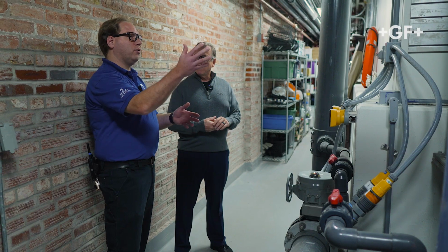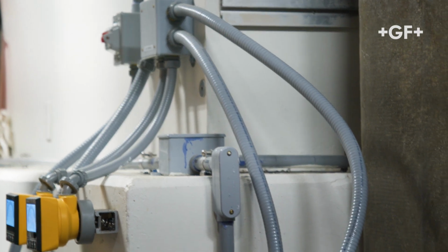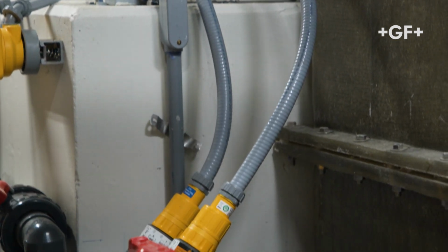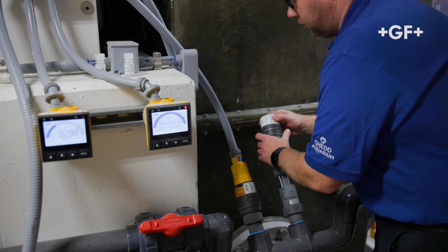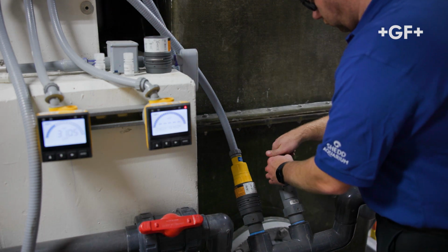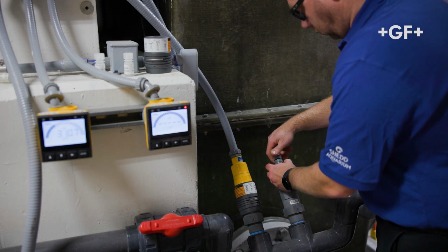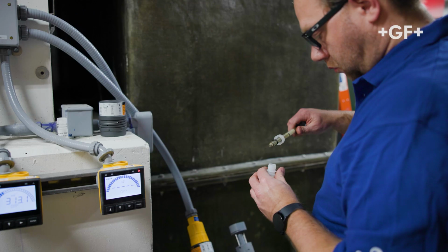The water has gone through our deaeration tower, and this would be the ORP that's entering the exhibit. The awesome thing about these wet tap assemblies is I can come up here and remove that probe without getting wet, without having to isolate the system. We can maintain live water flow without having to shut anything down.